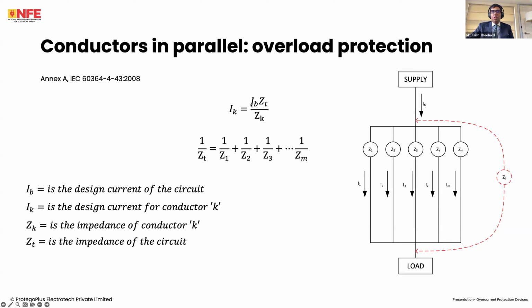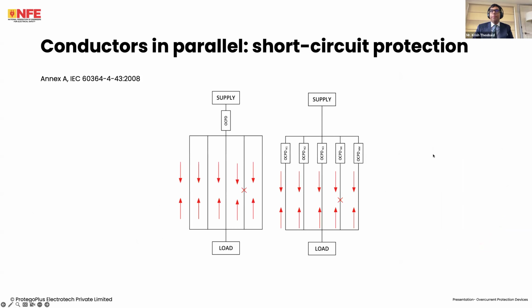IB is the design current of the circuit. IK is the design current for conductor K. ZK is the impedance of this conductor K. And ZT is the impedance of this whole circuit. So all the conductors in parallel.